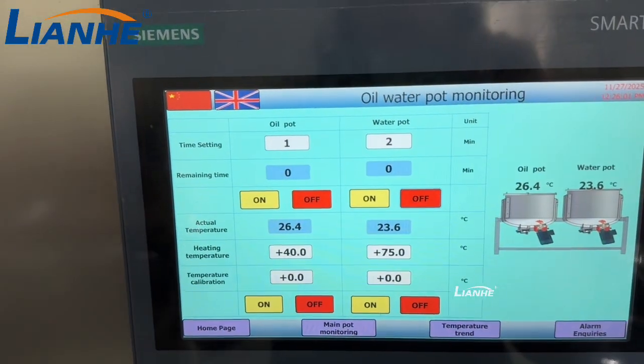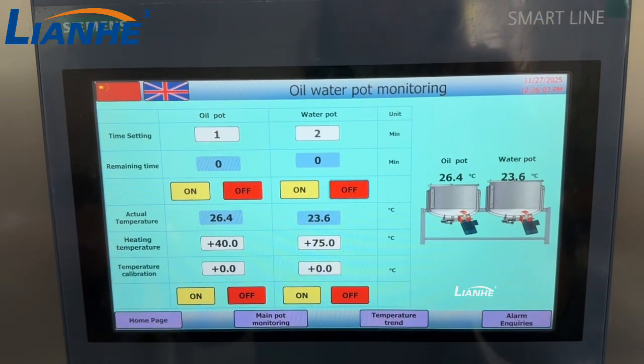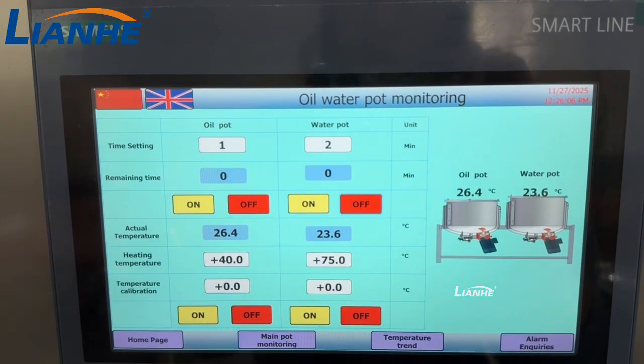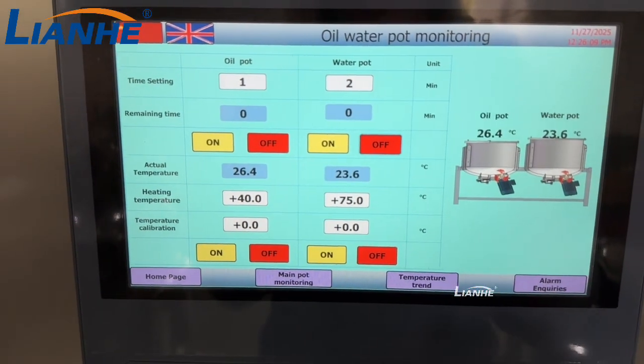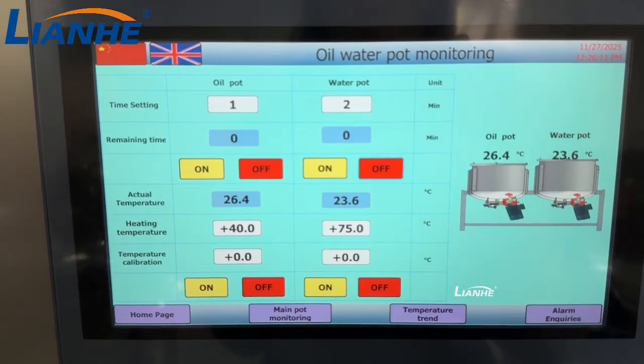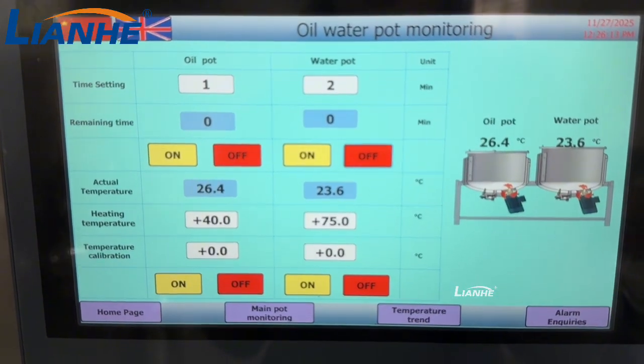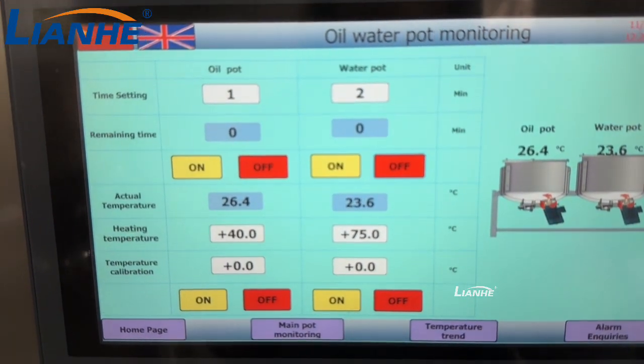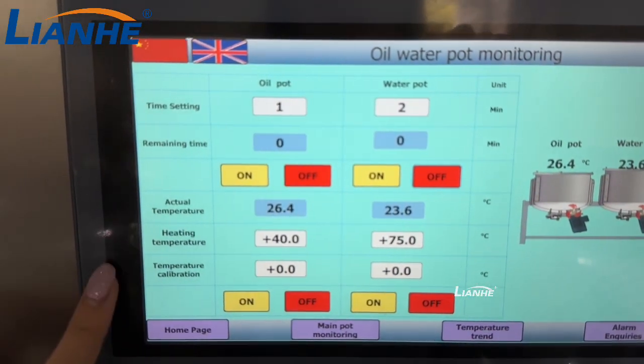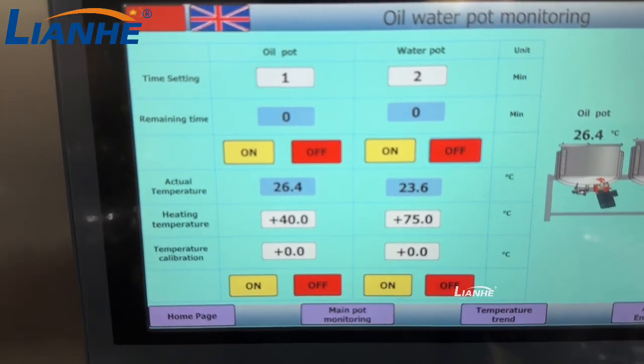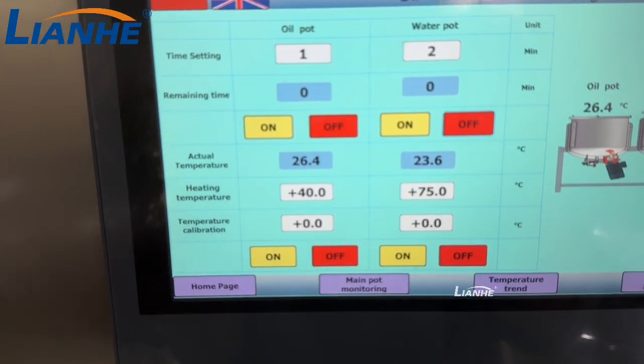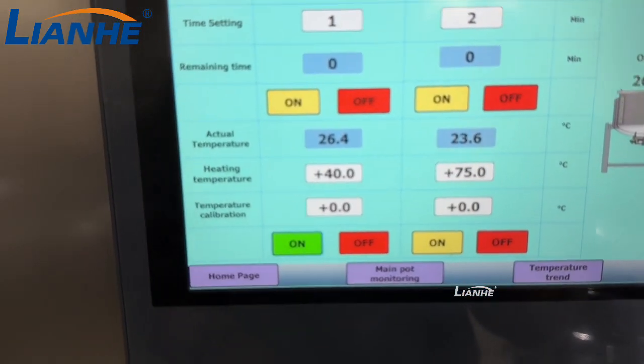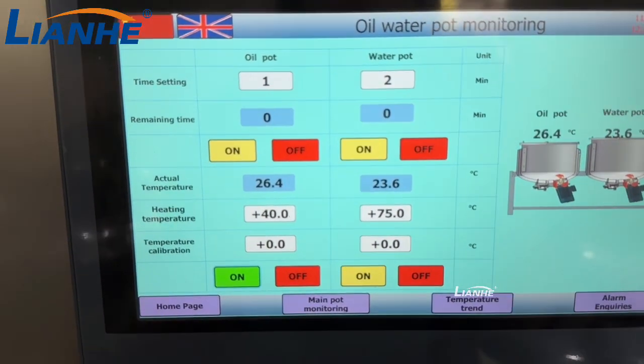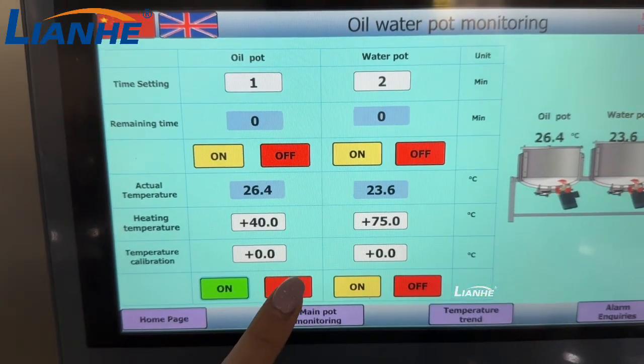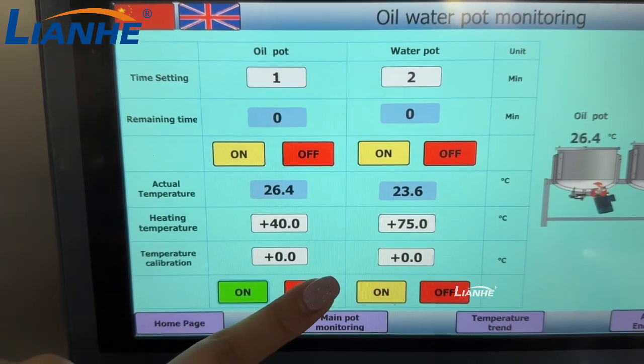And then for the heating function, like we just said, for the water tank and oil tank, our engineer has already put the heat transfer oil into it, so you can directly use the heating function. Make sure no water is inside your water tank and oil tank jackets. And this calibration is the same as I just said for the main tank, and then we can test it here for the oil tank, the heating temperature here, can test it, and then can turn it off.